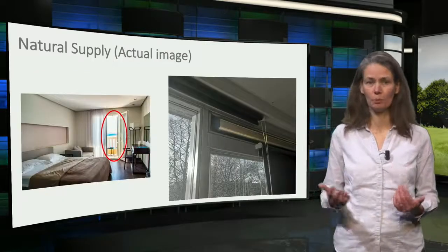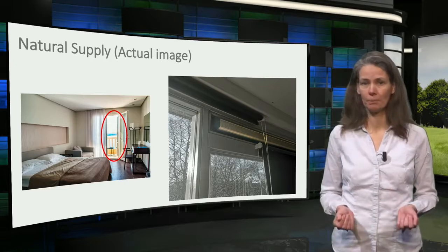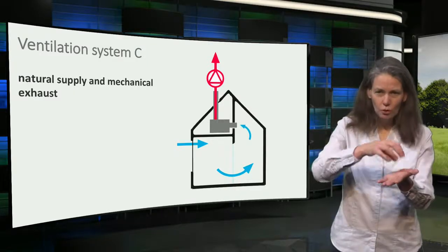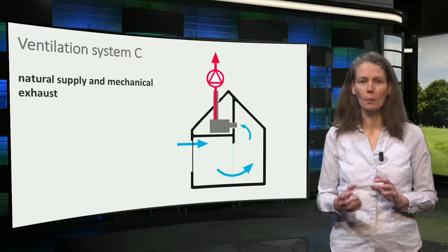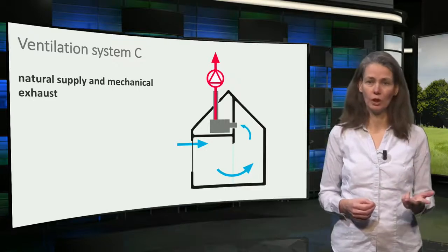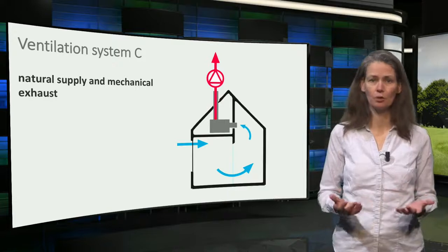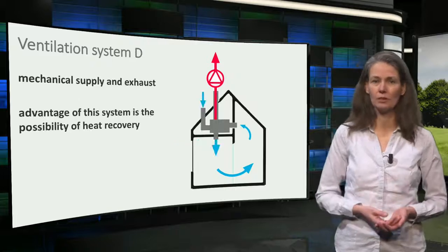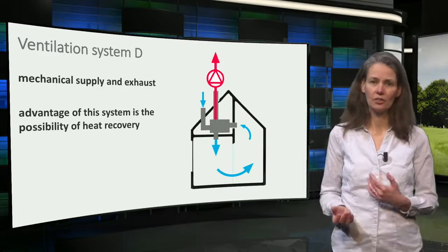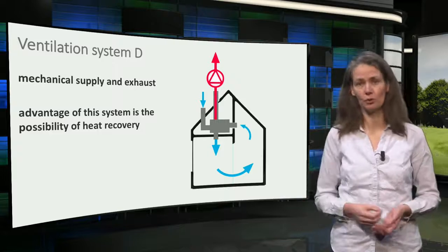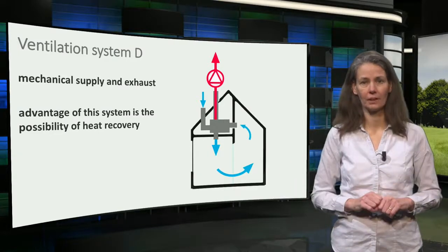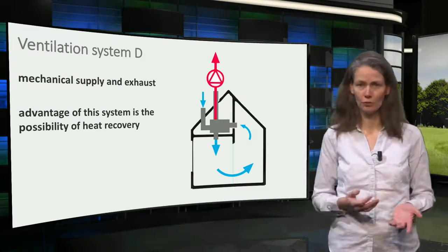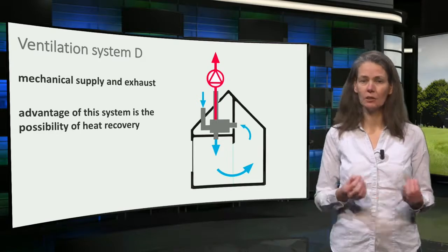The actual supply systems are given in this image. The air that is supplied to the room must also leave the room and preferably directly at the source of the pollutants. In the Netherlands, a mechanical exhaust is prescribed in kitchen, bathroom, and toilet for dwellings. A natural supply and mechanical exhaust system is called system C. A more advanced system is system D, which controls both the supply and exhaust amount of air and is therefore a balanced system. Another advantage of system D is the possibility of heat recovery, which will be discussed next week in the reuse step.